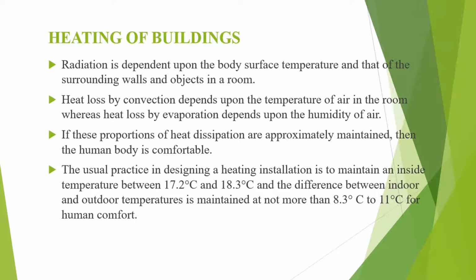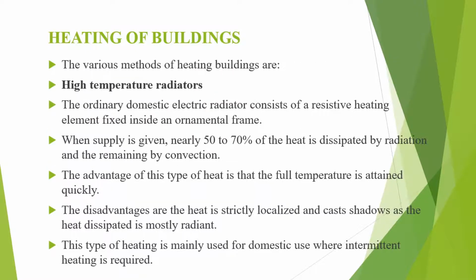The usual practice in designing the heating installation is to maintain an inside temperature between 17.2 degrees Celsius to 18.3 degrees Celsius, and the difference between indoor and outdoor temperatures is to be maintained at 8.3 degrees Celsius to 11 degrees Celsius for human comfort. The various methods of heating the buildings are high temperature radiators.